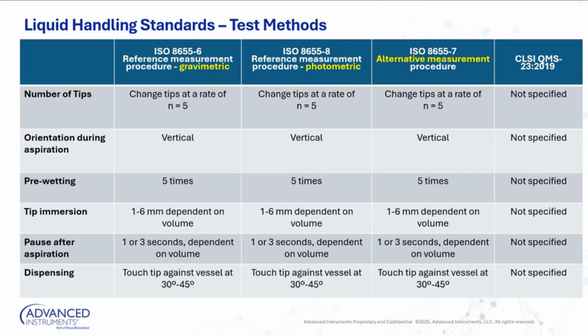The second row that you see is the orientation during aspiration. When you're aspirating, the pipette should be held completely vertical. If you're going through the lab and you're seeing your pipette operators holding the pipettes at angles, they're not getting the correct volume. So that's specifically called out. Pre-wetting is another technique that's called out in all of the ISO standards, and I'm going to talk a little bit about pre-wetting in just a moment. Pipette tip immersion depth is also called out in the ISO standards. They recommend 1 to 6 millimeters depending on the volume.